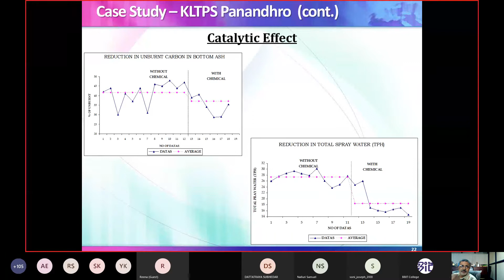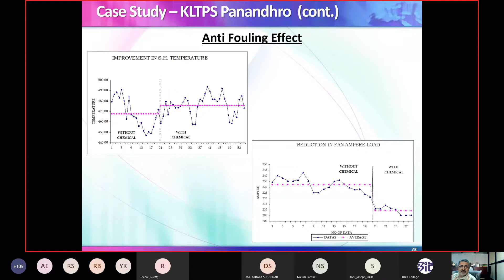So this confirms. The second one is the improvement from the anti-fouling effect. The superheated steam temperature has increased. Without it was somewhere about 467 and with it has gone to 475 degrees centigrade. So the improvement in superheated steam temperature shows that the surface has become cleaner. So that is the anti-fouling effect. Another important result is reduction in fan ampere load. If the resistance in the system reduces, your fan power has to reduce. So this is what exactly has happened. Your total fan ampere load was about 232 amperes. It has reduced to somewhere about 206 amperes. A sizable reduction. That means the auxiliary power consumption is also reduced to a very great extent.